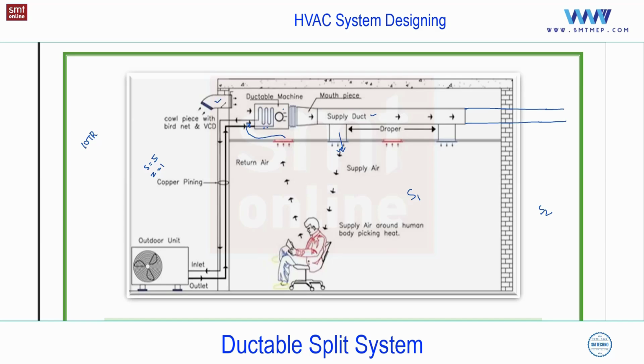You see, I can use this cowl piece. Call piece means a piece of duct which is bent down, and here you'll find the mesh. And this piece we need to design as per the fresh air requirement. For example, total CFM for this unit, say 5000 CFM as per the load calculation, and 10% of this I'm providing. So 10% of 5000 is 500 CFM.